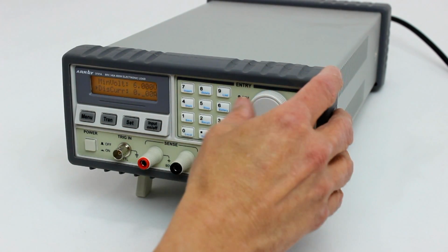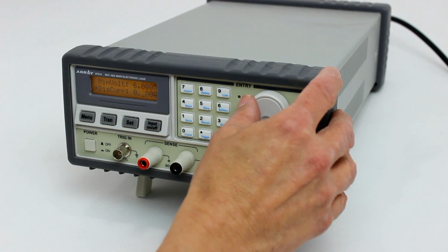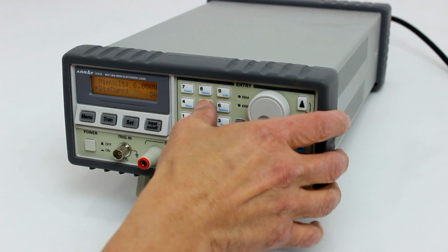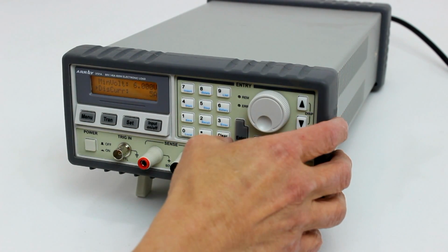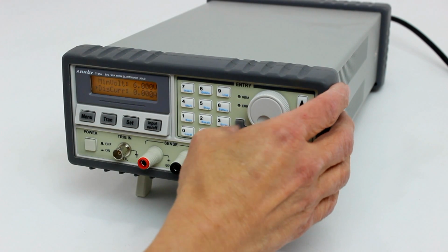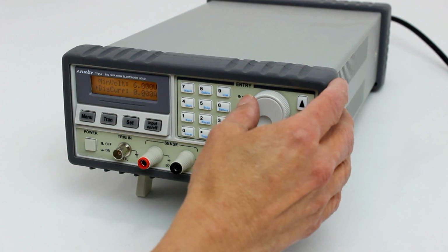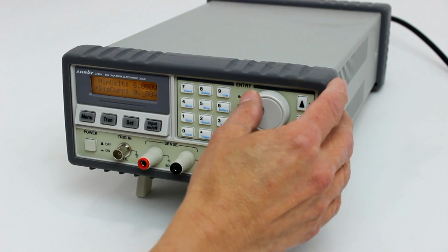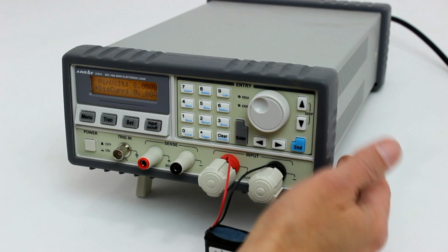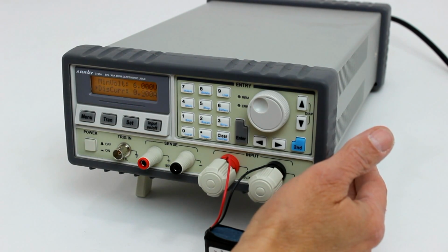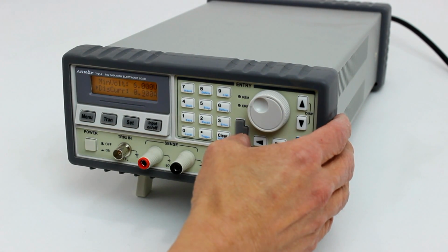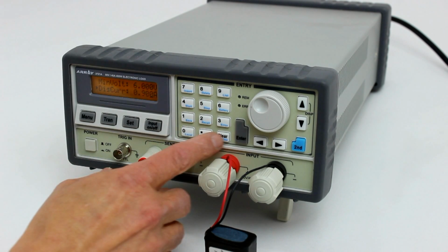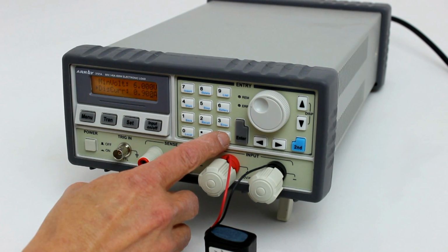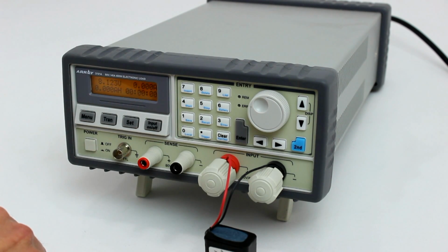Step 5. Press the input on-off button to begin the automatic battery discharge test. Step 6. The electronic load will proceed to discharge the battery at the discharge current value set in step 3, and will automatically stop the discharge test when the battery voltage equals the set value. You may then view the elapsed time required to discharge the battery and the amp-hour rating of the battery on the LCD screen.